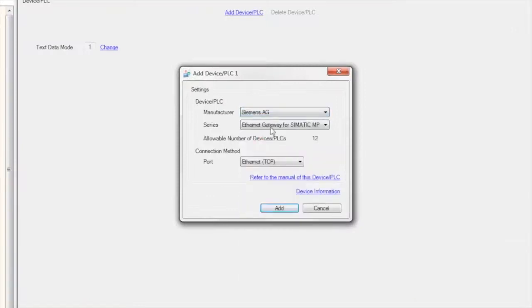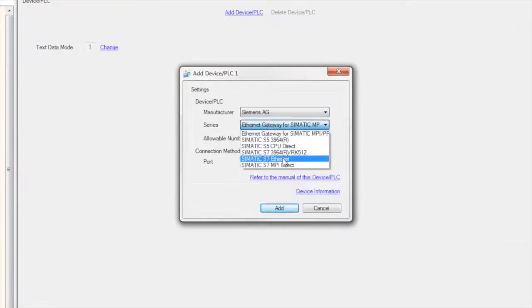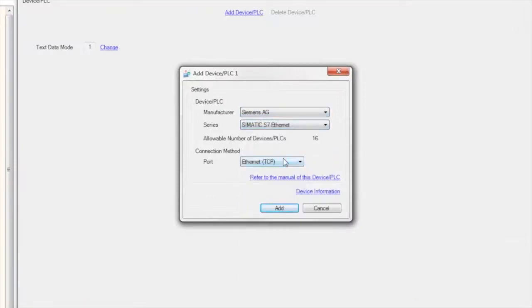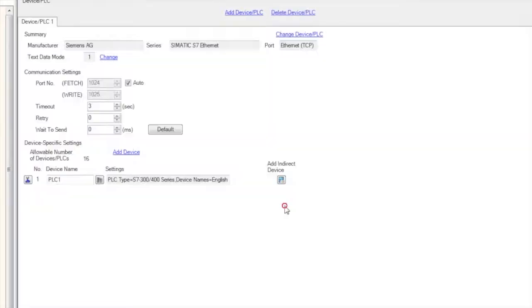For a Siemens connection to a Pro-face HMI, the first thing I want to do is add device PLC and then select Siemens AG and then select my protocol. In my case I have SIMATIC S7 Ethernet, essentially PROFINET, industrial Ethernet. Port TCP is the only option available, and from here I always like to give my device a name.